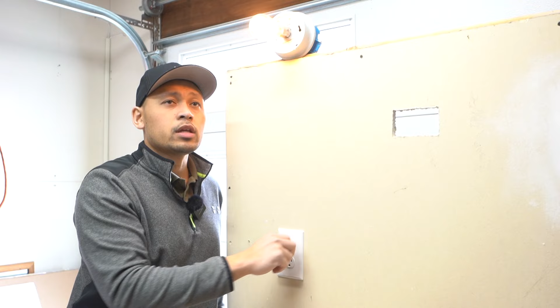So here you go, friends, let's test it out now. As you can see, the light switch is on, you can control it, and at the same time, you can go and plug this in, and you have the power still on. So at the same time, once you turn this off, the power on the outlet is constantly on. So again, that's the easiest way you can add an extra outlet inside your room without having to cut any drywall, run any wire, or put in any new electrical boxes, just by tampering inside one of your light switches, as long as you have a neutral wire inside that electrical box.